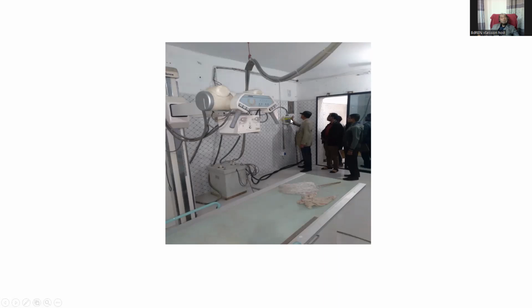And longer exposure time needs lower mA. So multiplication of mA and seconds is called dose. So we need to minimize the dose during the radiation. After repair, we need to calibrate the equipment according to milliampere, second and kV. We need to make a graph. And for a particular anatomical program, we need to select the voltage.